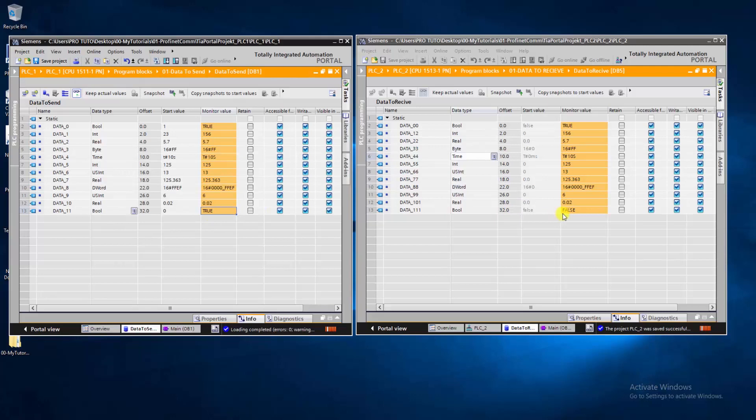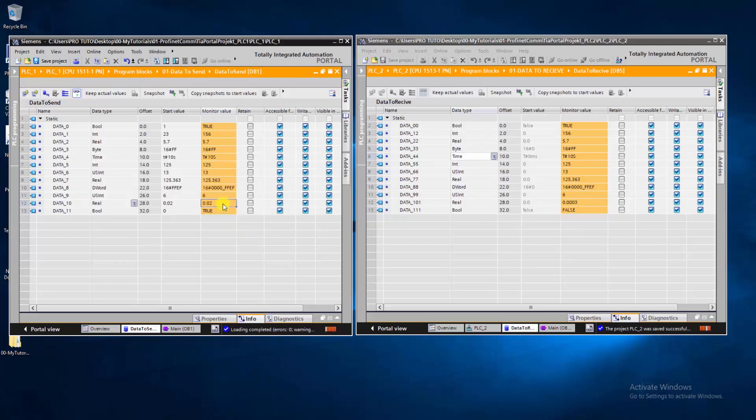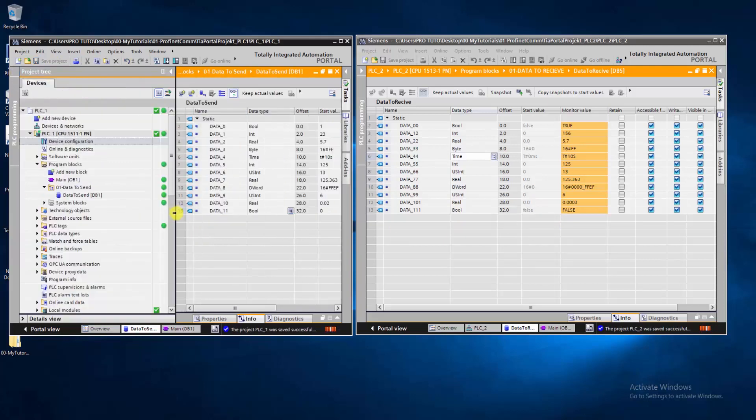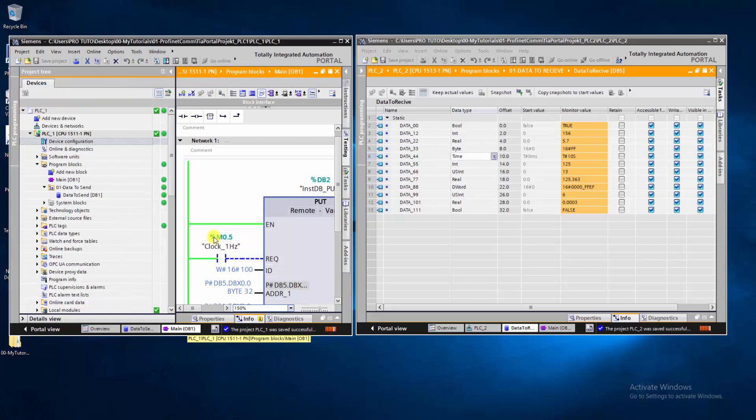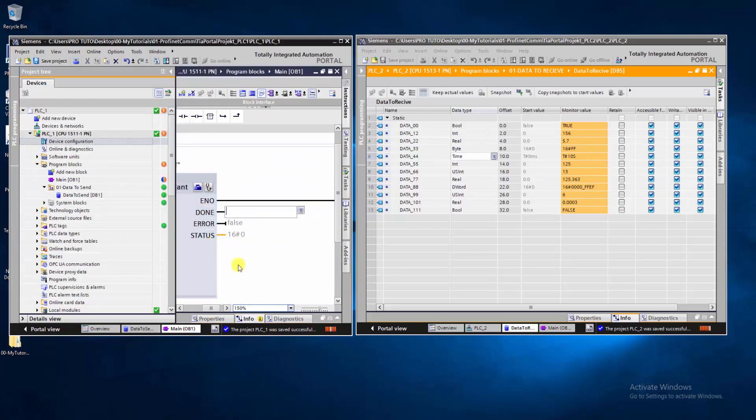Finally, we have the data as well put from PLC to PLC, updated every one second, but we noticed that the last element was not transferred. So, we have to check the amount of data transferred between the two PLCs.